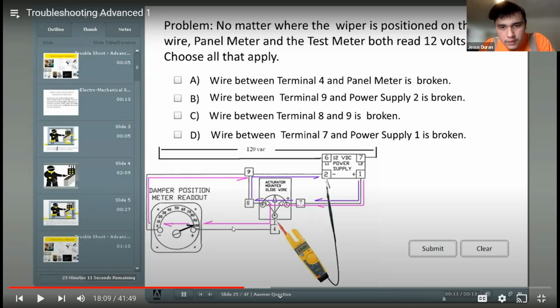to 2. And another reason I say that is because it looks like the meter's getting the full 12 volts also. It's all the way over to 100% open. And you see the other side of the meter goes back and uses wire 2 to 9, so we know that wire is probably pretty good. Otherwise, the meter wouldn't say squat. So that leaves us with what? That'd leave us with just the actuator mount slide. Leaves us with number C.